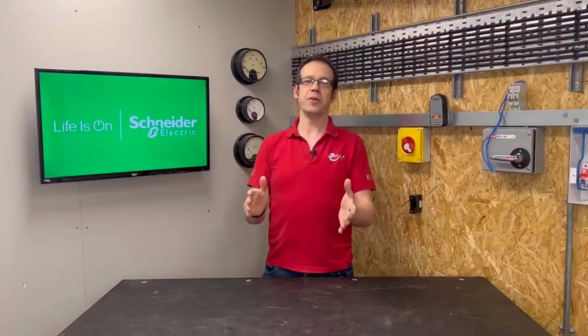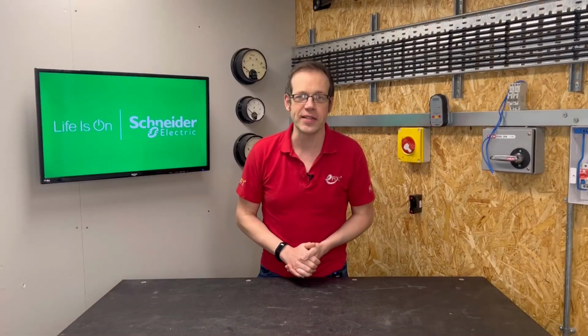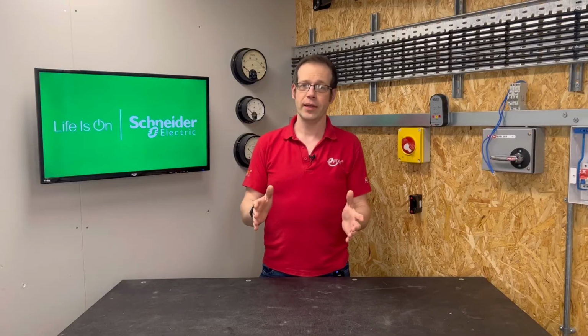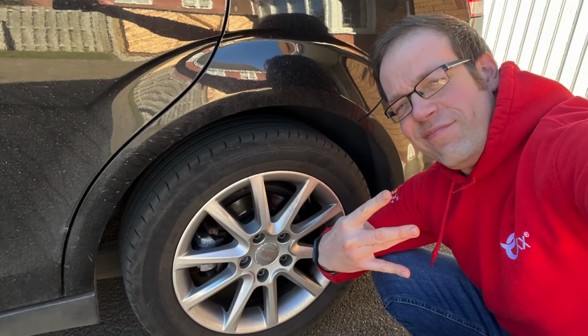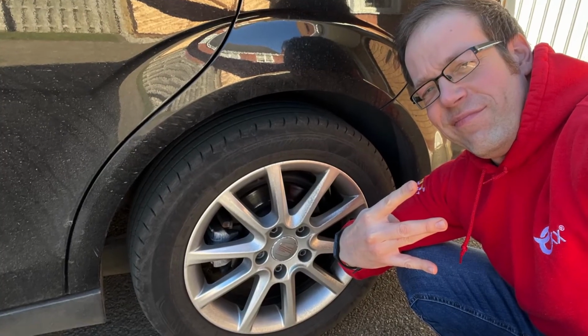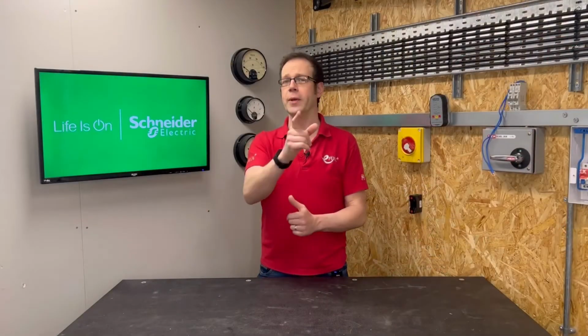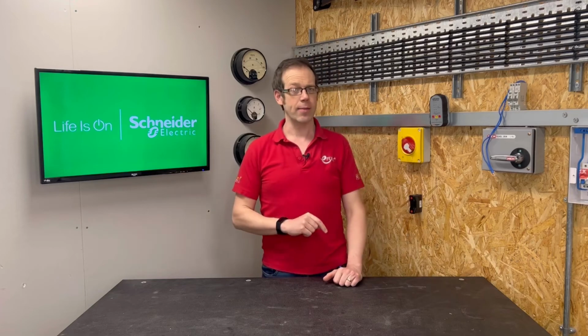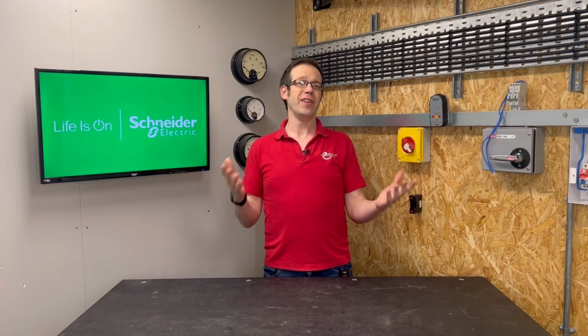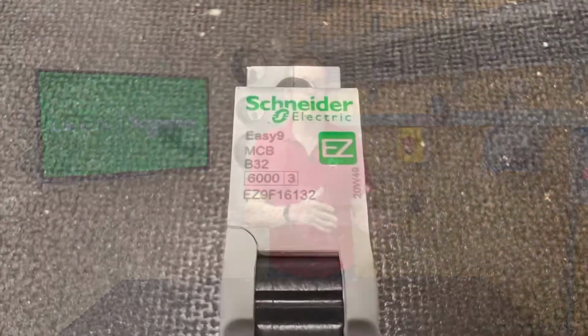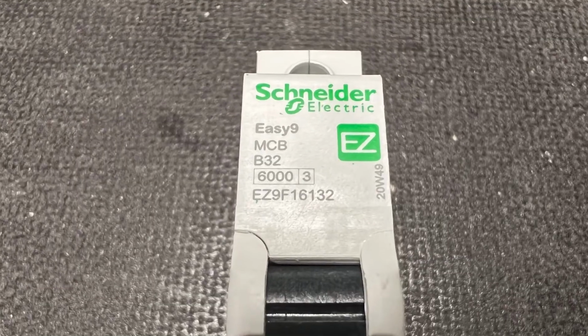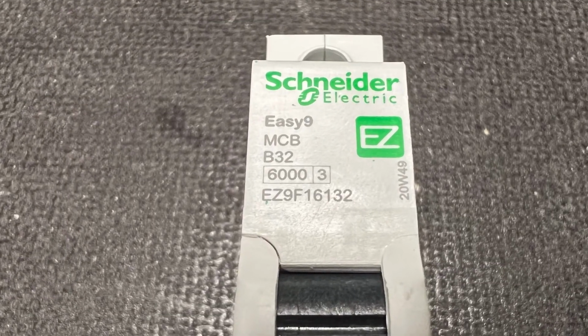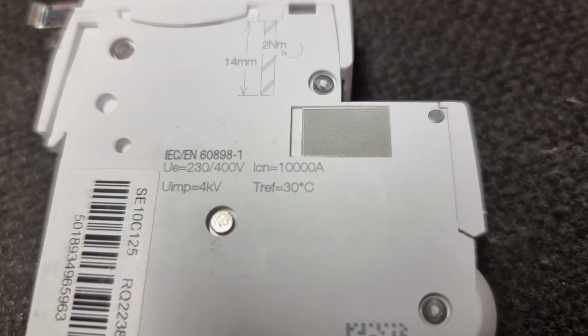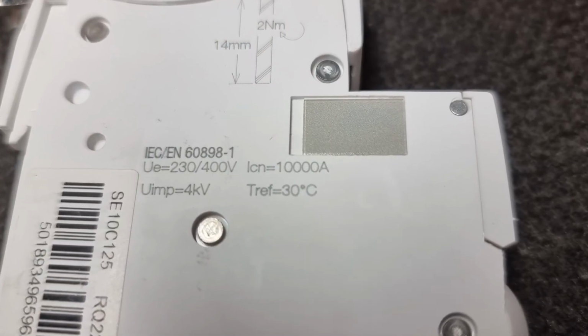If when you go to install your overcurrent protective devices you notice they're of the higher rating, then there's no need to worry. I liken this to the tyres fitted on my car. If they're rated at 100 miles per hour and I drive at 70 miles per hour, then they're going to be just fine. So no speeding, as it's unsafe and illegal in this example. So in conclusion, for domestic installations, circuit breakers rated at 6 kA will usually suffice. However, if you're looking at industrial or commercial installations, you may need to fit the higher rated 10 kA devices instead.